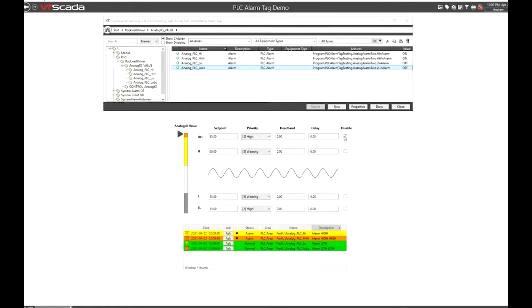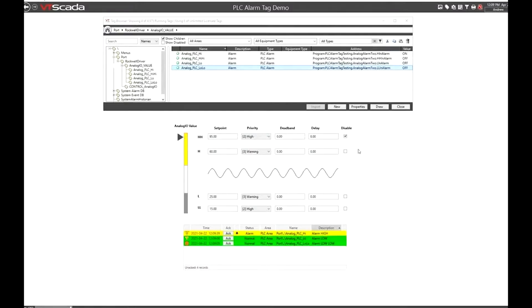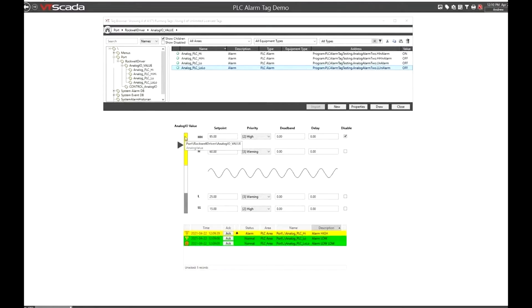Again, even if I disable here I'm issuing a control action from here but it's the PLC address which is determining that the alarm is disabled and we're reading that back to show that we no longer have this alarm.